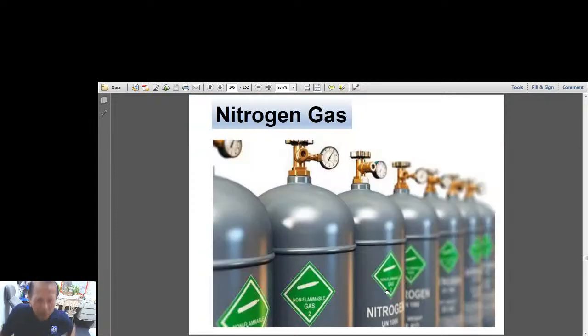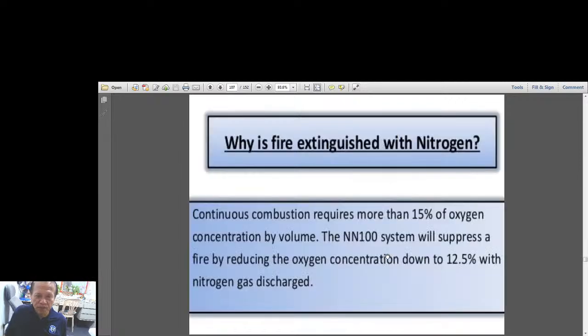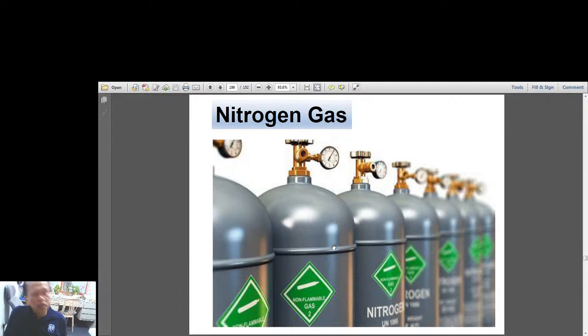Okay. So nitrogen gas can also be used. The air is 80% nitrogen roughly and 20% oxygen. Okay, so therefore nitrogen is plenty in the atmosphere. So you just need to produce nitrogen gas. You can also have equipment that can produce nitrogen at site, no? In other words, near the place of application, you can have equipment that produces nitrogen, which can already be injected to your room. But of course, it must be not occupied, because the moment you introduce plenty of nitrogen inside the room, then you are displacing oxygen. Okay?